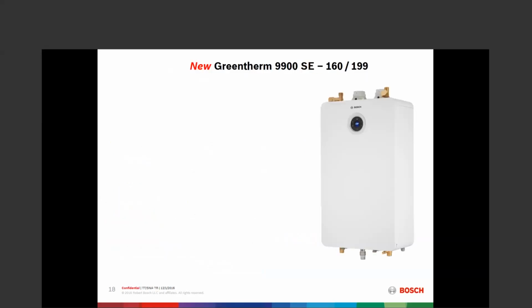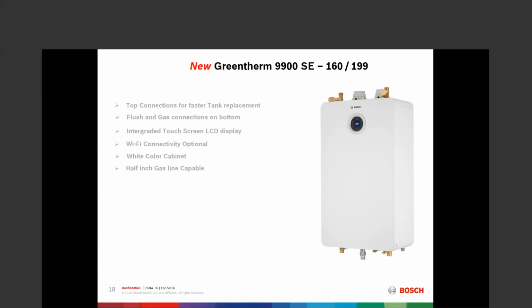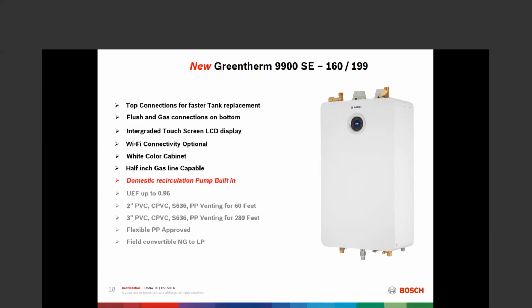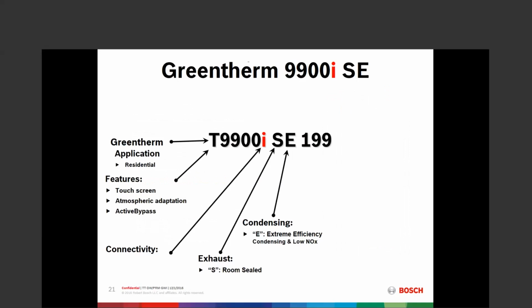So as you can see, the 9900 looks almost exactly like the 9800. There's no additional porting, so there's no return port for domestic recirculation. The domestic recirculation returns to the cold water inlet of the unit, so there's no additional connections to make. And as far as for that domestic recirculation, it doesn't matter whether that's coming back on a dedicated line or whether that's coming back on the cold water line with a crossover. Either way will work. Capabilities for production of hot water, all the same, the difference being that built-in ability to run domestic recirculation. Then the capstone, the T9900i.